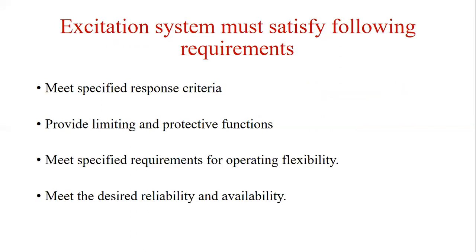Now let's see the excitation system requirements which it must fulfill for the power system. First, it needs to meet the specified response criteria. It must provide limiting and protective functions as required to prevent damage to itself, the generator, and other equipment. It should meet specified requirements for operating flexibility. And it should meet the desired reliability and availability by incorporating the necessary level of redundancy and internal fault detection and isolation capability.